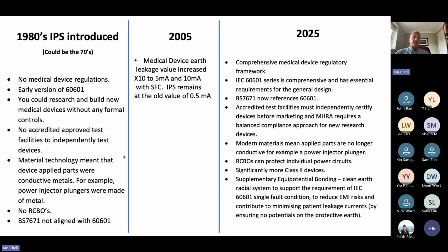Moving to 2005, another crucial value to be noted is that in 2005, the earth leakage value for medical devices increased 10 times to 5 milliamps, and 10 milliamps with a single fault condition. And IPS remained at the old value of half a milliamp. So please remember that.